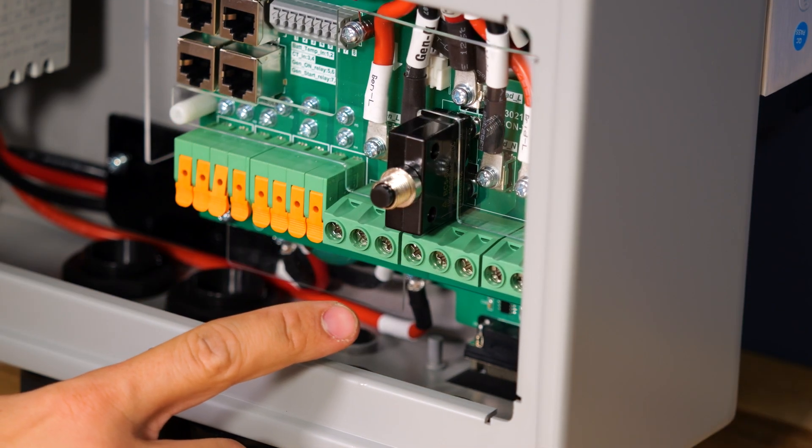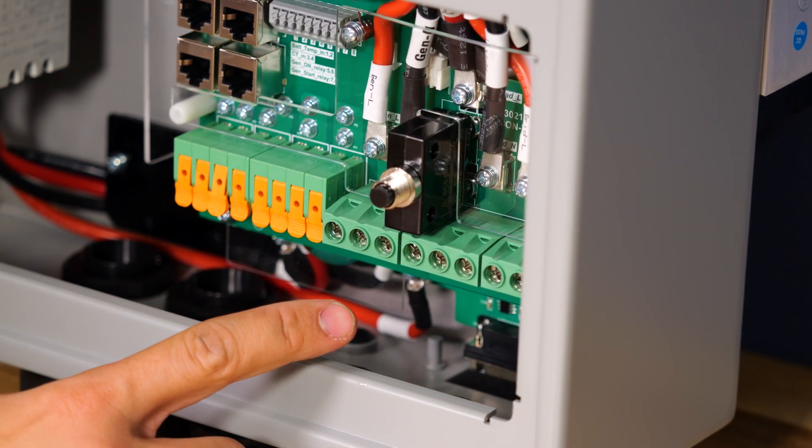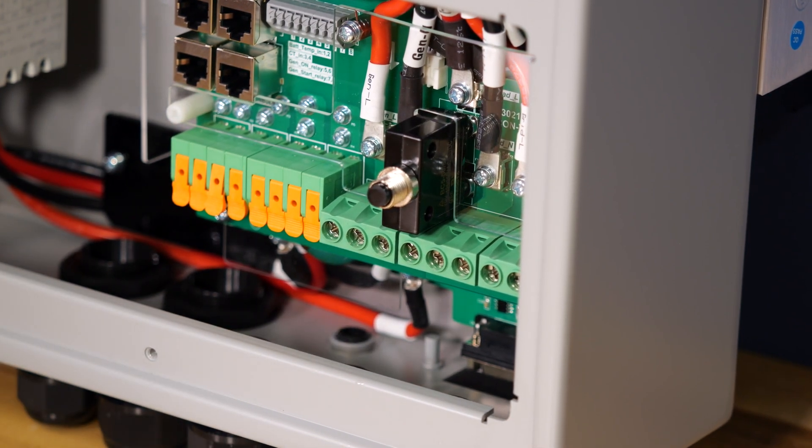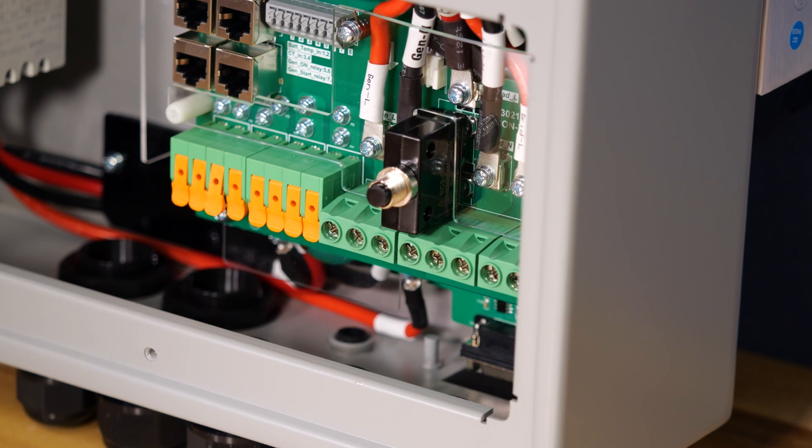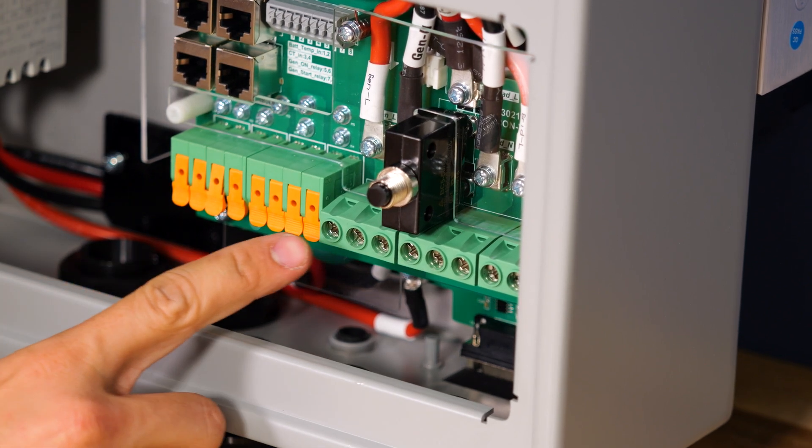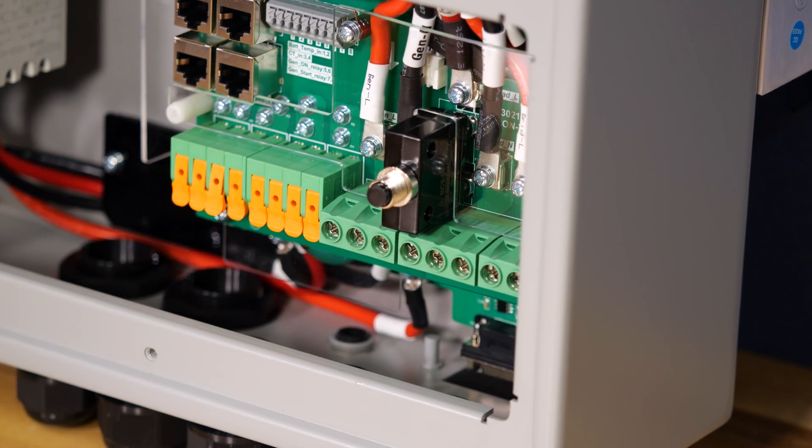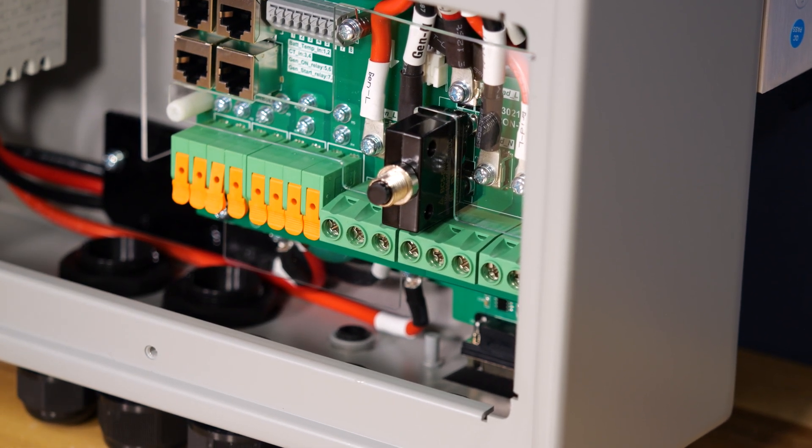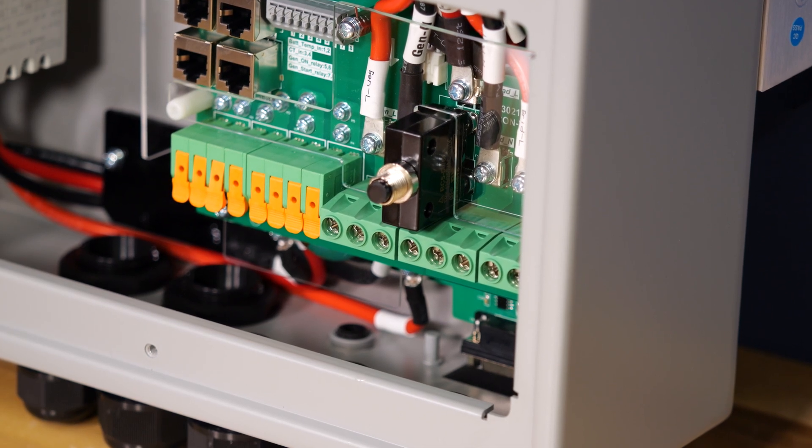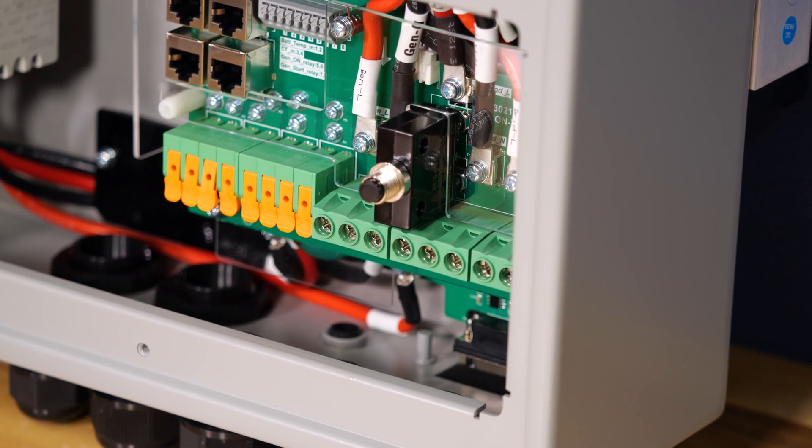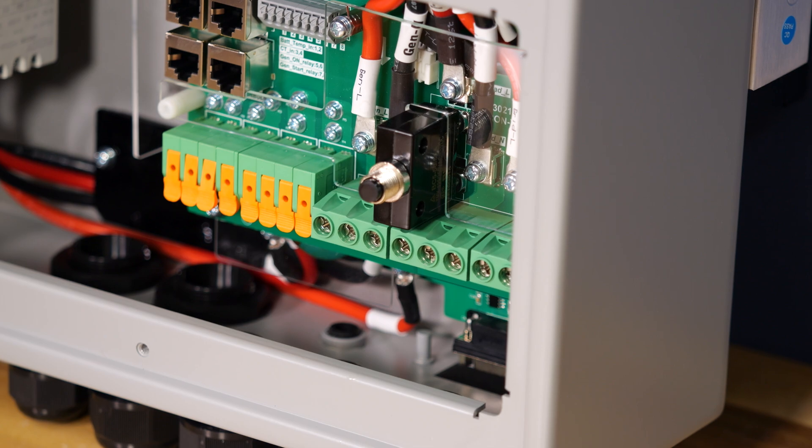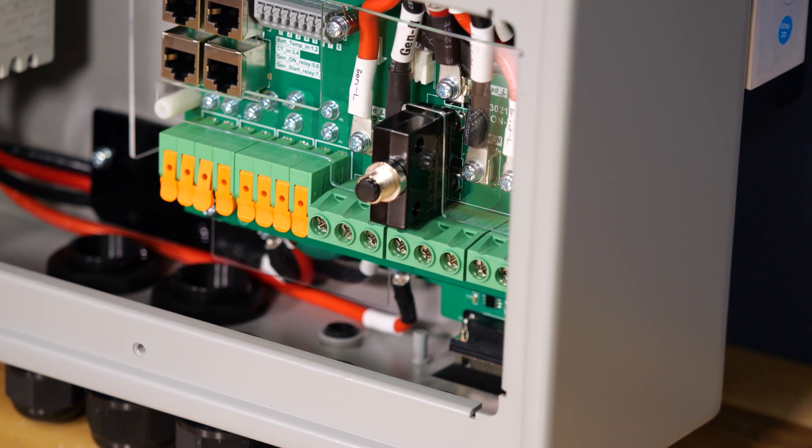These AC terminals support up to 50 amps and can fit six gauge wire just fine. However, the gen terminal is limited to 30 amps maximum and that can be used for either a generator or for AC coupled PV if you wanted to use this inverter as the main controller in an off-grid system.